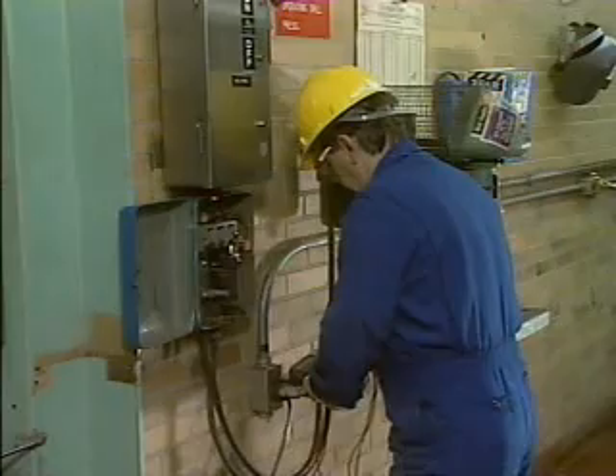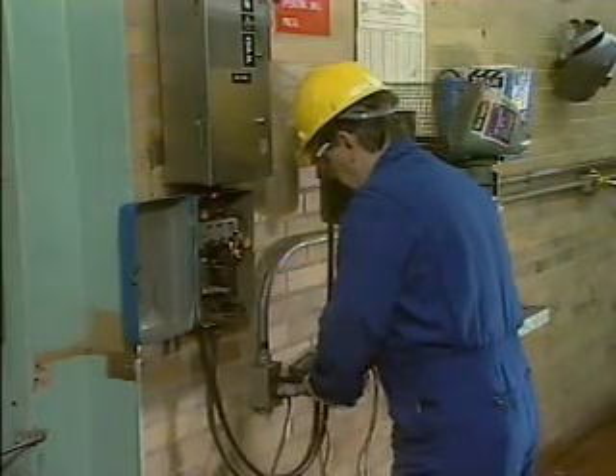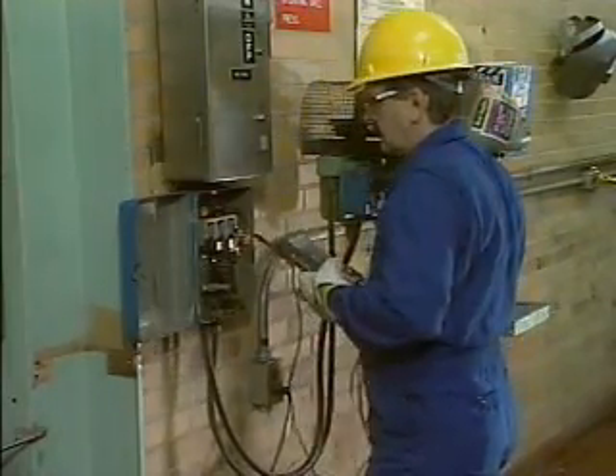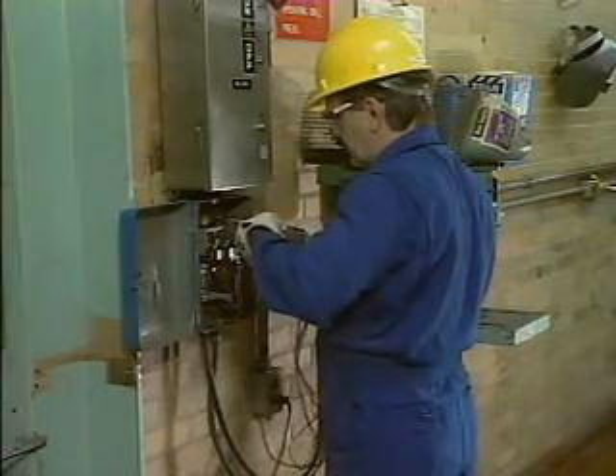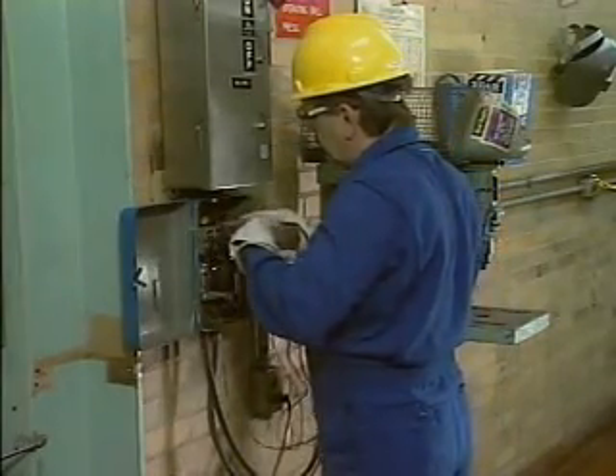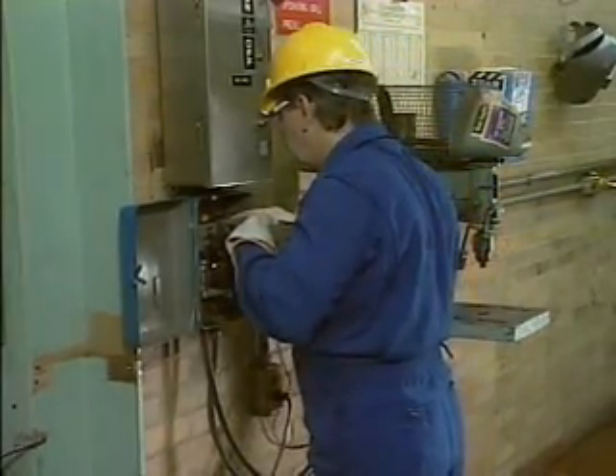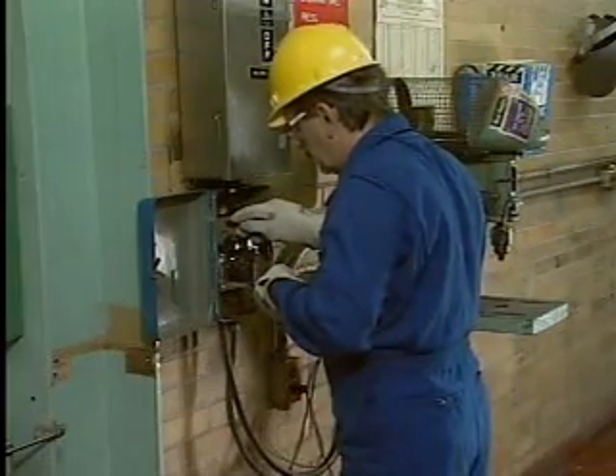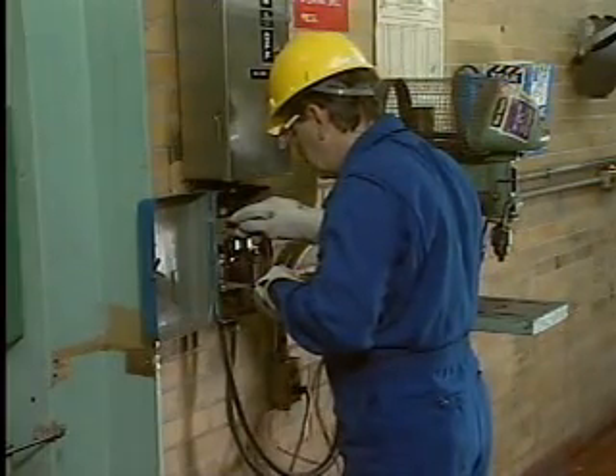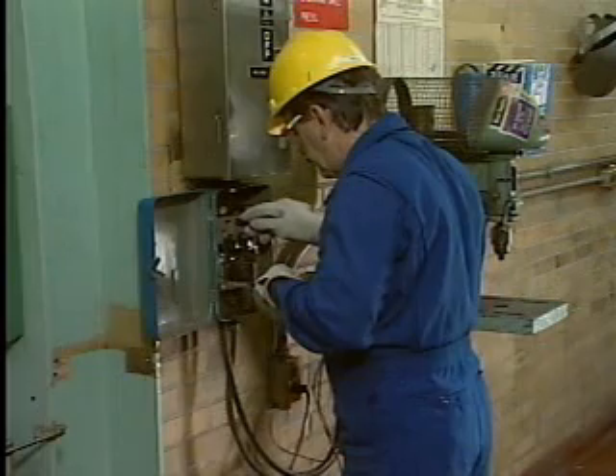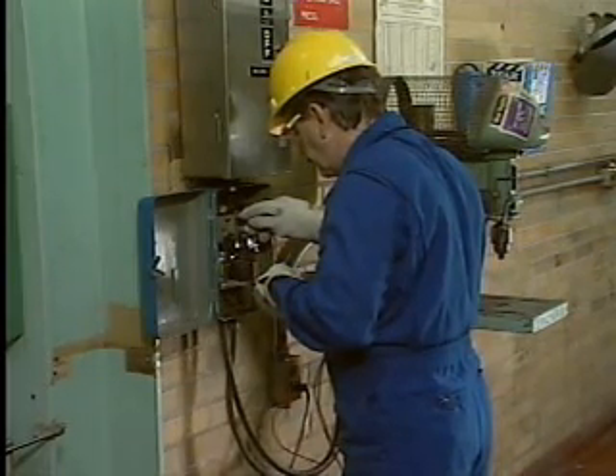After the electrician finishes his inspection, he checks his voltmeter at a nearby wall outlet. To check the circuit's operation, he measures the phase-to-phase voltage where the power lines terminate inside the cabinet. He then measures the voltage from each phase to neutral. The results of these measurements indicate that the circuit has the proper operating voltage.